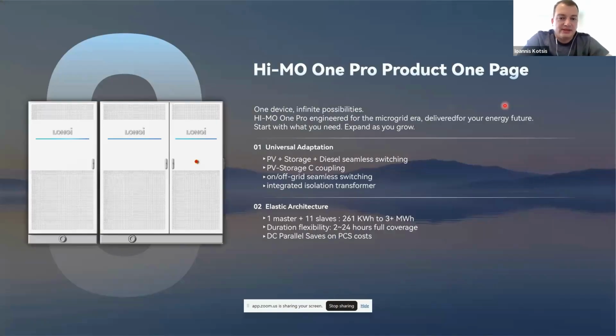The difference with the new one, the HI-MO ONE Pro, is that this is a more project-specific product. It can be a standard solution, but it can also be very project specific, because we offer a lot of options. We can have DC coupling through this battery, a DC-coupled system, or AC coupling, and it's highly flexible. We can have up to 11 slave units, so in total it can reach 3 megawatt hours. Depending on the configuration, you can have up to 24 hours of functioning, depending on how much you want to increase the capacity.